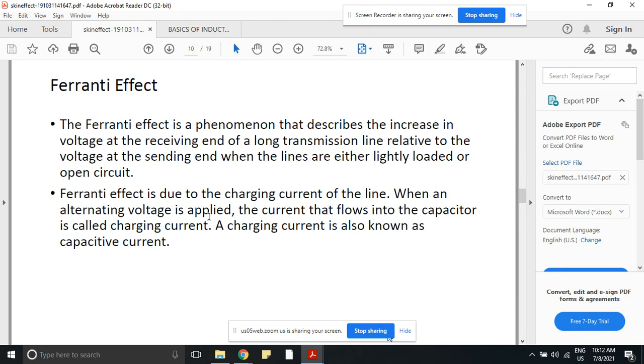When an alternating voltage is applied, the current that flows into the capacitor is called charging current. A charging current is also known as capacitive current, because for long transmission lines we cannot neglect the effect of capacitance. So what you have to write for this question: define Ferranti effect and state the causes. First point, Ferranti effect is observed in long transmission lines. Second point, because of this effect, the receiving end voltage will be greater than the sending end voltage. The third point is that this phenomenon can be observed in long transmission lines which are lightly loaded or open circuited, that means no load conditions.